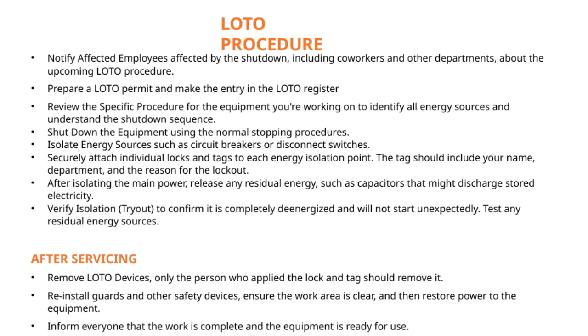Next, verify isolation by performing a tryout. Confirm that the equipment is completely de-energized and won't start unexpectedly. Test residual energy sources to ensure safety before proceeding with work.